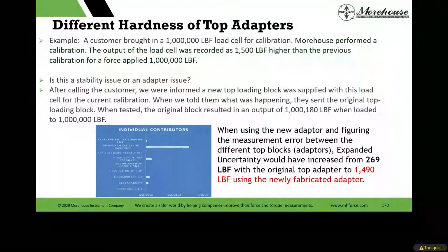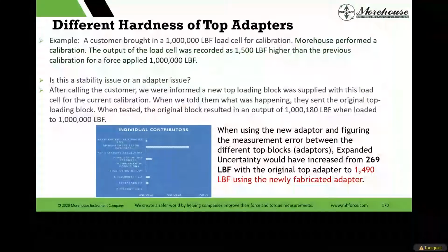Look at if there's 3 years worth of data, and I just took some numbers. I'm gonna look back and see if anything's trending, if anything looks weird. And on this load cell, I kept digging, and I'm like, wow, this load cell's pretty stable. I wouldn't have questioned 250 pounds out of a million, maybe even 500 pounds out of a million. Though on this load cell, all of a sudden I see a 1,500-pound shift.